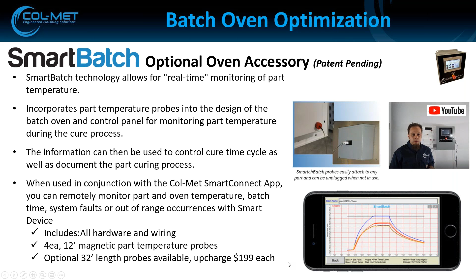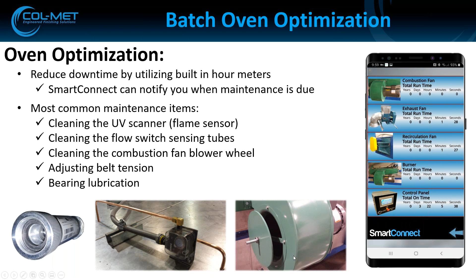So I just wanted to cover a few of the most common items that can lead to downtime, which costs you money. The Smart Connect app has the built-in feature that monitors the devices, as I mentioned earlier. Whenever a device is nearing a maintenance point, it'll just send you an email. And remember, you can set up groups so that those emails will go to a maintenance department. That way you're not getting bombarded to a plant manager that may not really care about a belt that needs to be tensioned or anything like that. But some of the most common things that we see that can shut an oven down are a dirty UV scanner, clogged flow switch, fan wheel on the combustion blower, incorrect belt tension, and then bearing failures due to lack of lubrication.